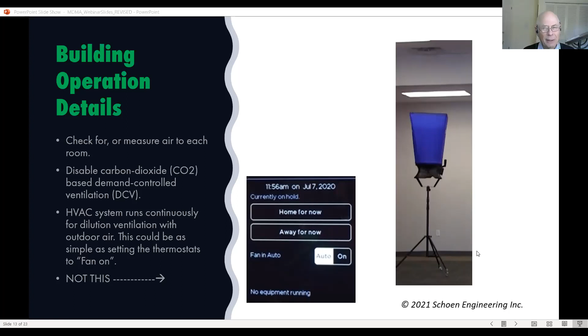Now, for a VAV system, it's not as simple as switching the switch on a thermostat to fan on. In a VAV system, it's called variable air volume. Now you have one large central air handler that's often controlling multiple zones by virtue of dampers and controllers that often look something like this, with the damper blade connected to the top left of that device. And for thermostatic control, they reduce the airflow to each room.